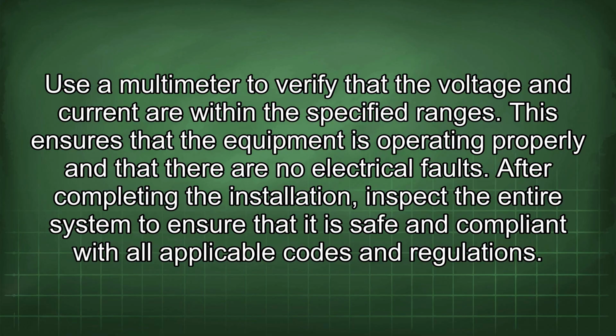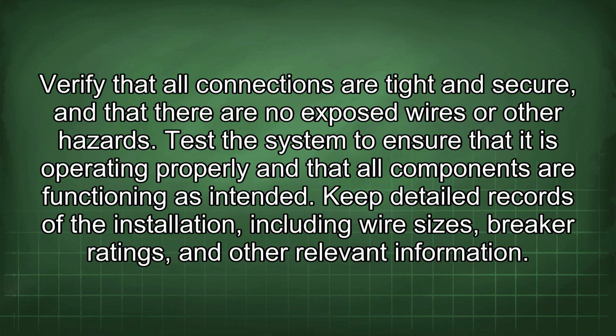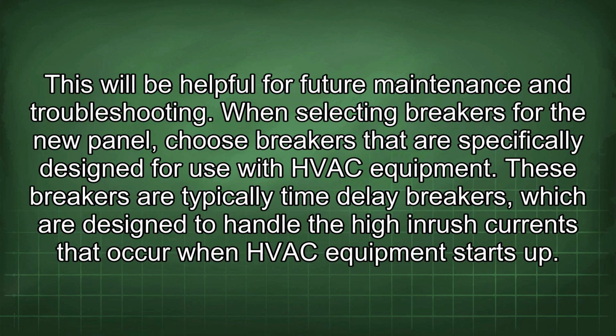After completing the installation, inspect the entire system to ensure that it is safe and compliant with all applicable codes and regulations. Verify that all connections are tight and secure and that there are no exposed wires or other hazards. Test the system to ensure that it is operating properly and that all components are functioning as intended. Keep detailed records of the installation, including wire sizes, breaker ratings, and other relevant information. This will be helpful for future maintenance and troubleshooting.